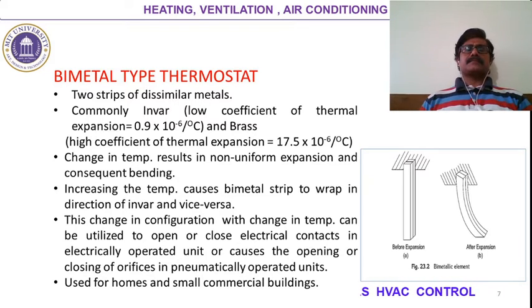The principle of operation of this thermostat is based upon the change in temperature. The change or variation in the temperature results in non-uniform expansion and the consequent bending, or change in the shape, of this bimetallic strip. If there is an increase in the temperature, it causes the bimetal strip to warp in the direction of the low coefficient of thermal expansion. And if there is a decrease in temperature, then the vice versa action takes place.